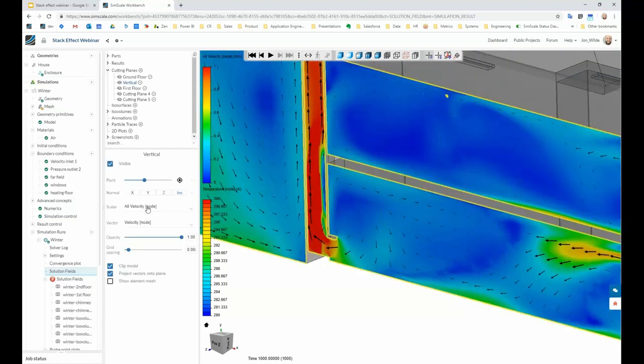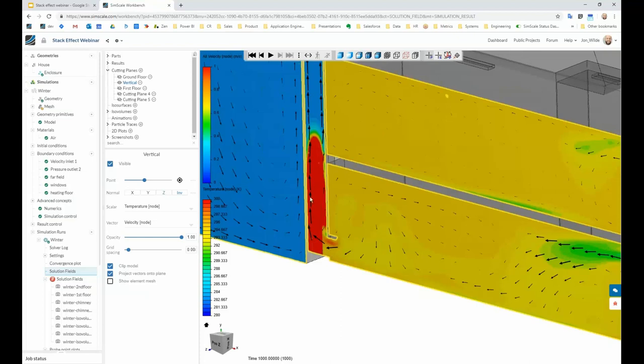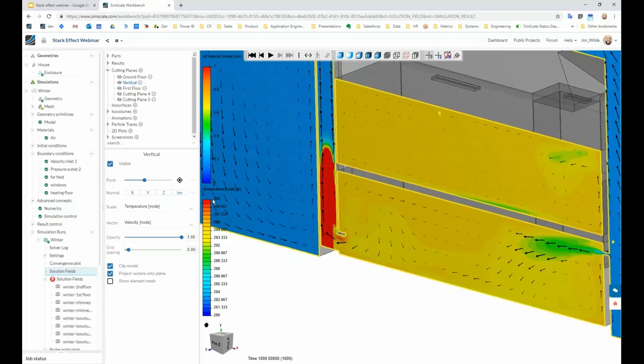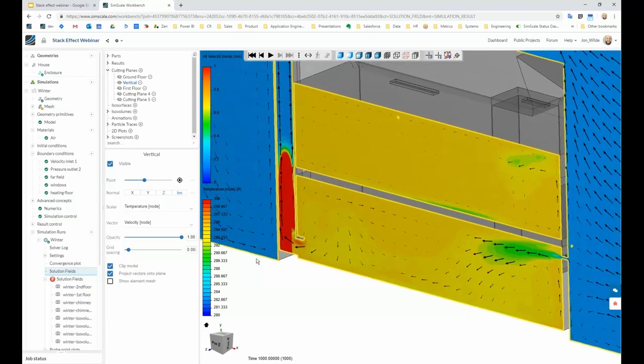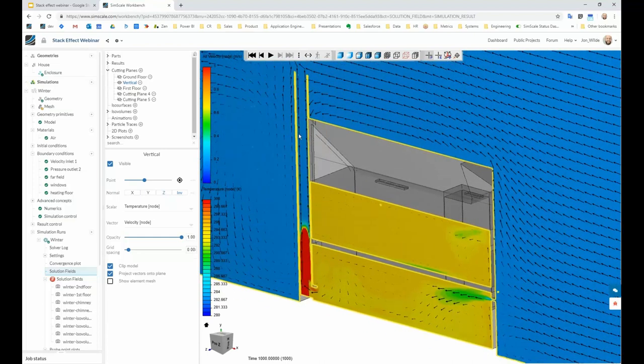This is answering the initial question: what is happening to the flow inside, and is it getting pulled out of the chimney? The answer is definitely yes — we can see all the flow exiting the chimney. This is partly due to pressure but predominantly due to temperature from the fire below. If I change the cut plane from velocity to temperature, we can see the air temperature in the room and see it heating up near the fire. The scale runs from 280 to 300 Kelvin. Most of our occupants, we want them around 295–300 Kelvin to be comfortable, and that is where we're at. The flow is heated by the fire, density drops, it rises and exits through the chimney, joining the flow passing over the building.